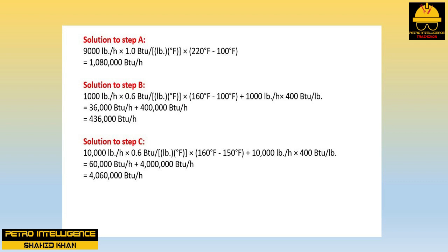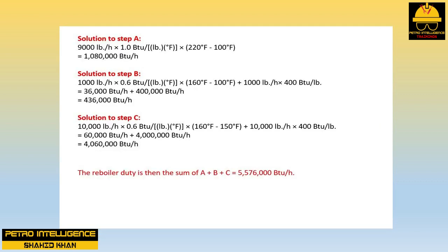Solution to Step B: 1,000 lb/hr × 0.6 BTU/lb·°F × (160 − 100)°F + 1,000 lb/hr × 400 BTU/lb = 36,000 BTU/hr + 400,000 BTU/hr = 436,000 BTU/hr. The reboiler duty is then the sum of A + B + C = 5,576,000 BTU/hr.